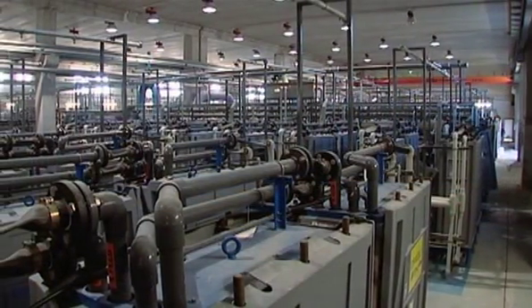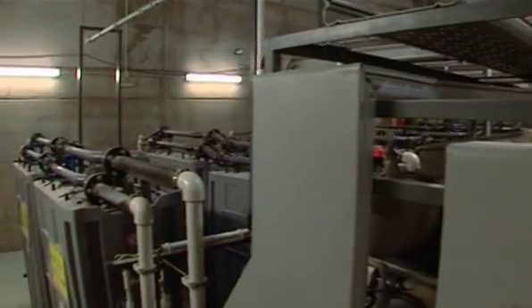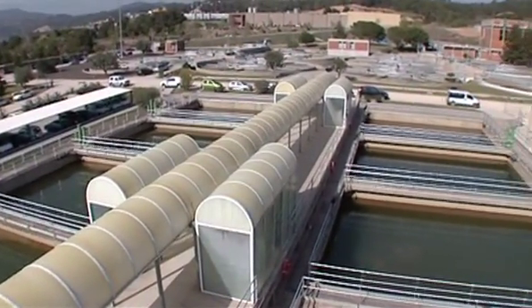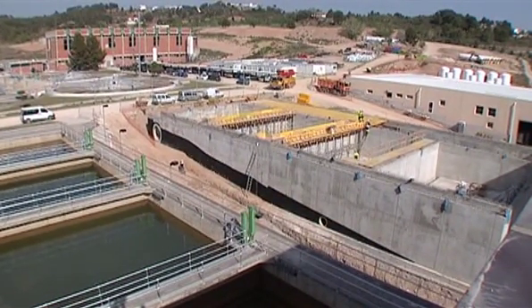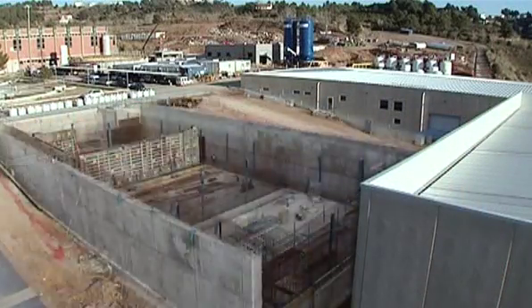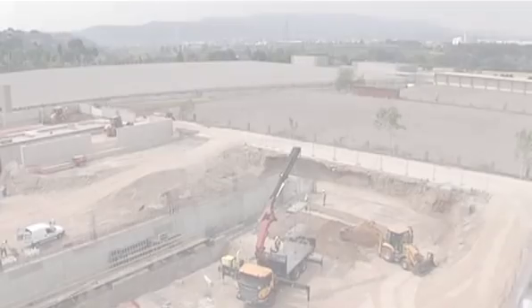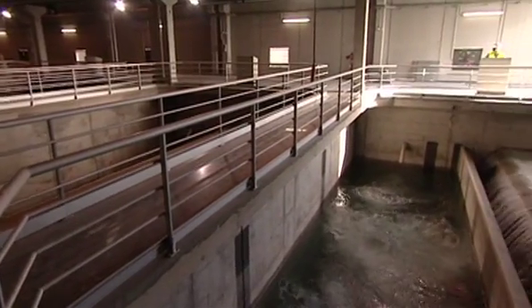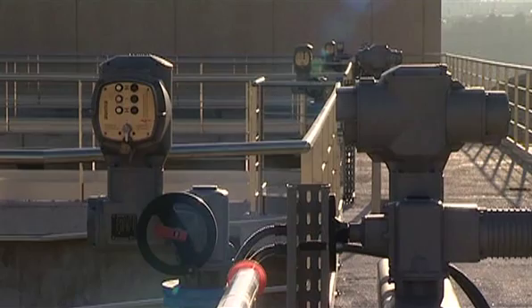The flow of the treated water has also increased from three to four cubic meters per second. The plant's filtration capacity has increased with the construction of four sand filters, which, added to those already existing, make a total of twelve. Five new activated carbon filters absorb the dissolved organic matter in the water along with the previous ten. These are new facilities incorporating technological innovations that serve to obtain an excellent quality of water.